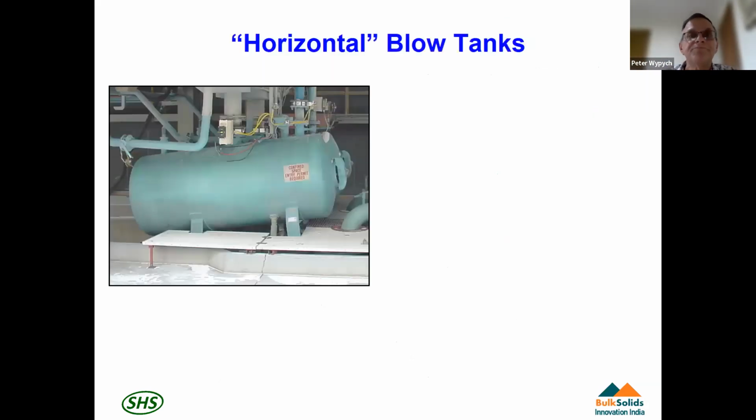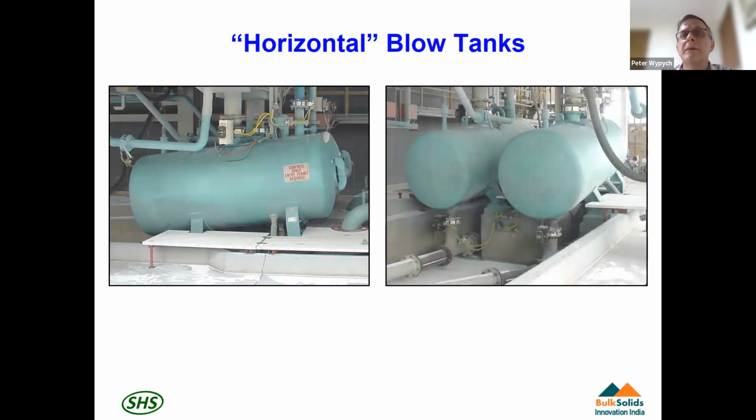Anyway, moving on. Some innovative blow tanks we're involved with. Haven't got time to show too much of this, but horizontal blow tanks for low headroom applications. So you can see there, this is for a tandem application. And this was a system that the client wanted to upgrade because they didn't have enough capacity. They wanted to get an extra 30%. They were prepared to increase the size of blow tank, pipeline, etc.